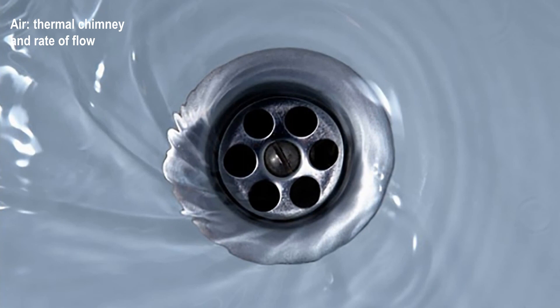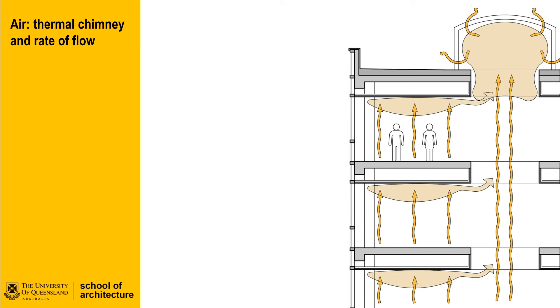We can draw upon another water analogy to visualise how hot air escapes from these trapped spaces. A full bathtub can only drain at a certain rate depending on the shape of the bath, how water is directed to the plug, the size of the plug, and perhaps the number of plugs. The natural flow rate is something we can try and control, but there are typically rates at which water and air like to flow. For buildings that use atria and buoyancy to generate airflow, it is important to make sure there is a reserve of space at the top of the atria that is sufficiently large to hold the trapped air as a buffer and capture it while it escapes at a certain rate. The number of outlets from the atria will also increase the efficiency of how quickly hot air can escape, but we need to balance this to ensure the whole system functions properly.